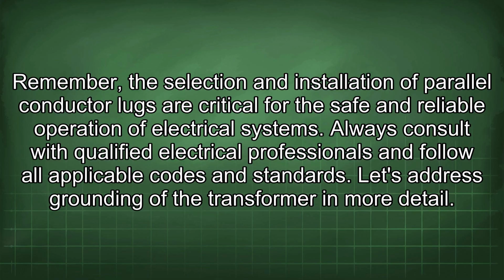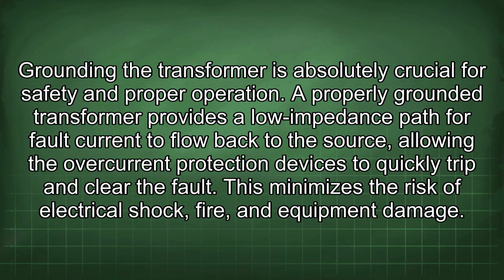Let's address grounding of the transformer in more detail. Grounding the transformer is absolutely crucial for safety and proper operation. A properly grounded transformer provides a low impedance path for fault current to flow back to the source, allowing the overcurrent protection devices to quickly trip and clear the fault. This minimizes the risk of electrical shock, fire, and equipment damage.